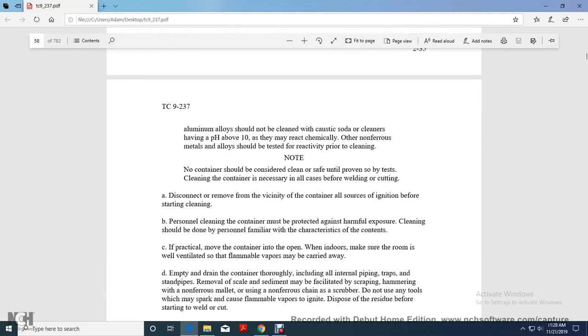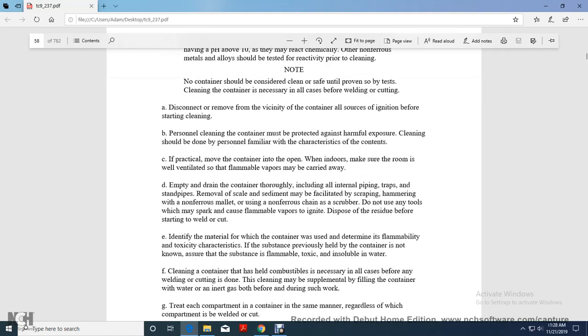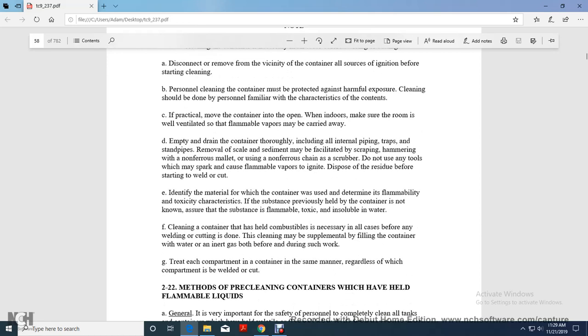No container should be considered clean or safe until proven so by tests. Cleaning the container is necessary in all cases of welding and cutting. Alright, disconnect and remove from the vicinity of the container, all sources of ignition before starting cleaning. Personnel cleaning the container must be protected against harmful exposure, but it should be done by a person familiar with the characteristics of the contents. If practical, move the container into the open, and when indoors, make sure the room is well ventilated so the flammable vapors may be carried away.